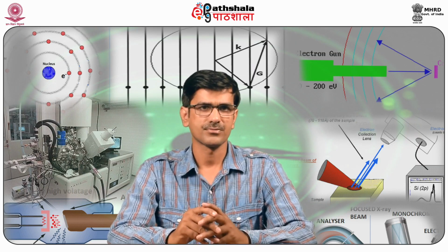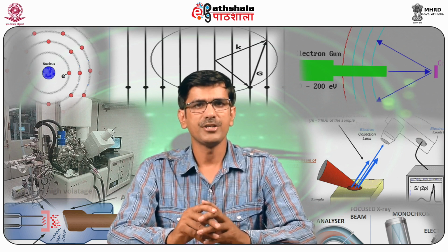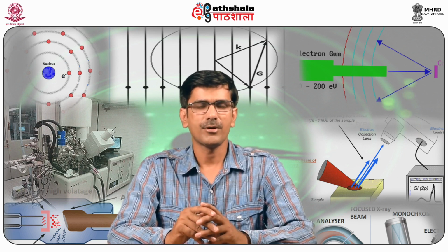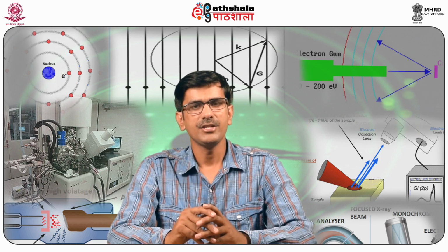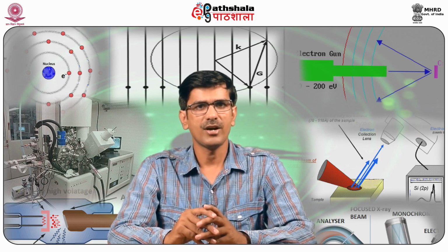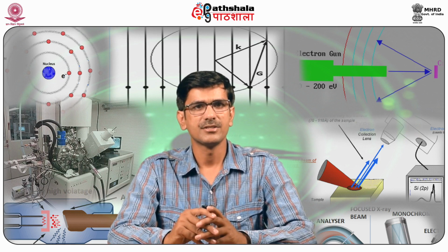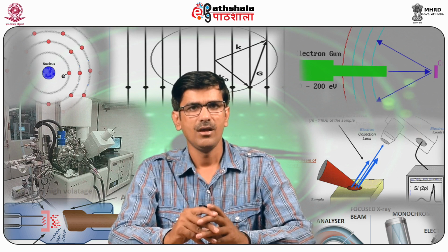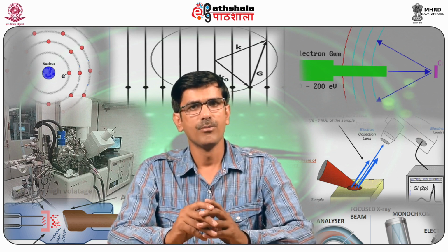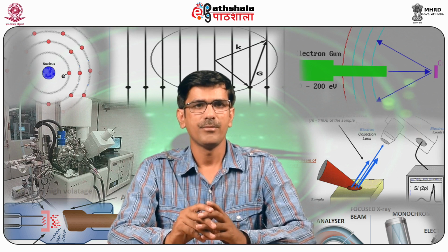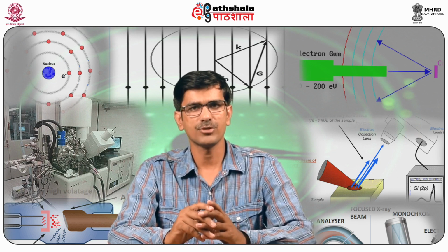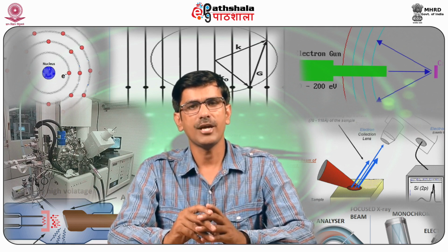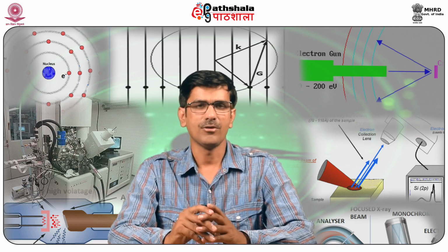The filters. XRD requires monochromatic radiation, but the beam not only contains the K alpha line but also the K beta line and the continuous spectrum. The intensity of the undesirable components can be decreased relative to K alpha by passing the beam through a filter. The filter also absorbs the K beta component more strongly than K alpha because of the abrupt change in absorption coefficient between these two wavelengths. The wavelength of the K alpha line is related to the atomic number by Moseley's law.